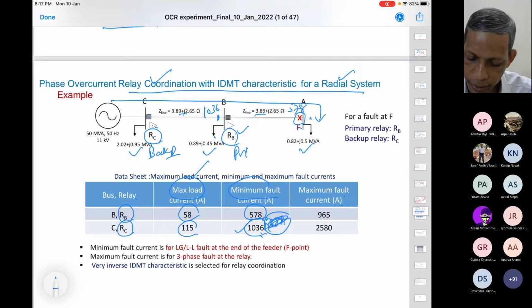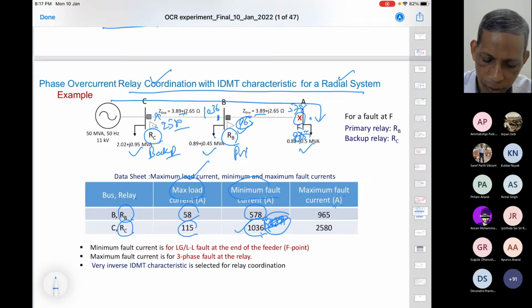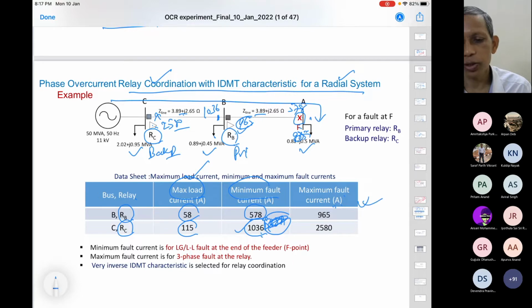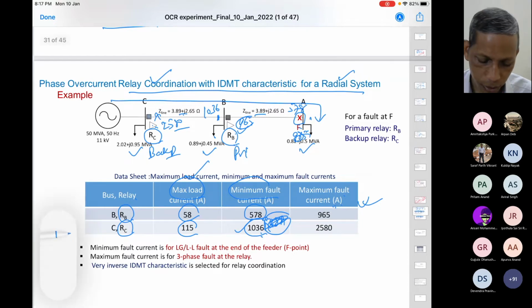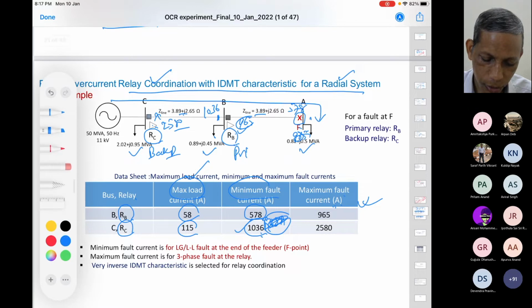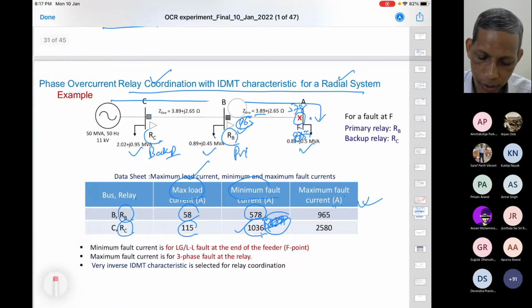We'll see that analysis. Now, maximum fault current at A is 965. If you create a three-phase fault at B, sorry, not A, this B, it is 965 here. And if we create a three-phase fault here, this gives you 2580. So from simulations, from the network modeling perspective, the data are available, which is being used by the protection engineer for setting up these things. Clear? So this is what is being used by different engineers.